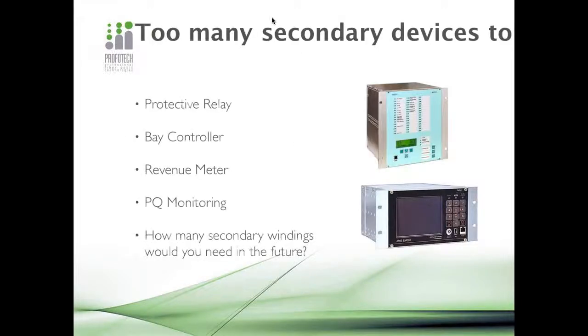So first is smart grid from the instrumentation point of view. Well, there are several problems we foresee when we go into smart grid that would definitely influence the instrument transformers. First of all, we have more and more secondary devices. For example, if we speak about some high voltage substation, then we have probably protective relays, the bay controller, the revenue meter, the power quality monitoring unit, and more and more devices that we should connect to secondary windings of the instrument transformers.